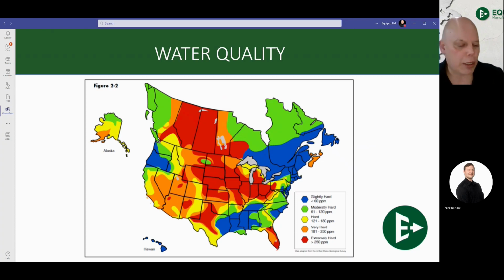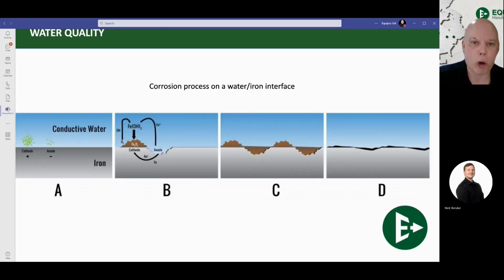Your other side of this conversation is the stuff that is non-ferrous, which is, well, for starters, your calcium, magnesium, lime scale buildup. Here's a little chart that we have of the hardness of water across North America. Well, it's exclusive of Mexico, but it's through Canada and the United States. Canada doesn't have, well, I'll talk about Ontario, doesn't have terribly bad water. Lower Quebec doesn't. Out in the Prairie provinces, extremely hard water. You could chew that stuff if you so desired, and that needs to be addressed because we have what's called mineral salts, and these mineral salts are your calcium, limes, and your magnesiums. I'm going to talk about that here in just a moment.